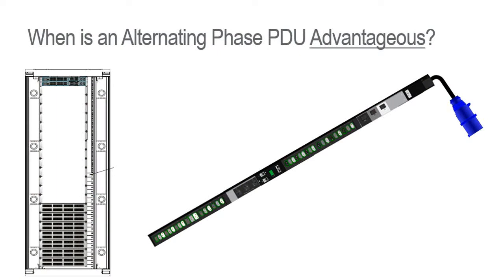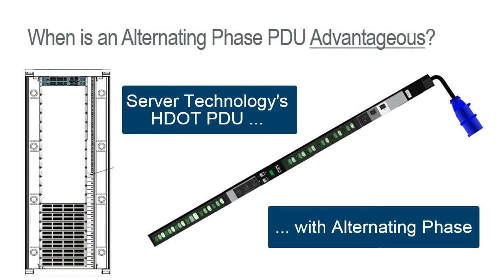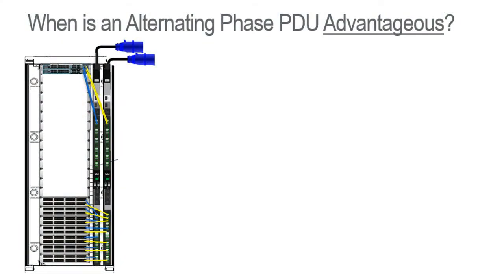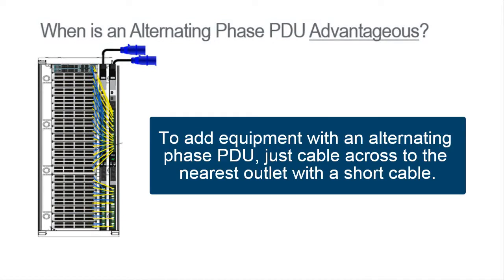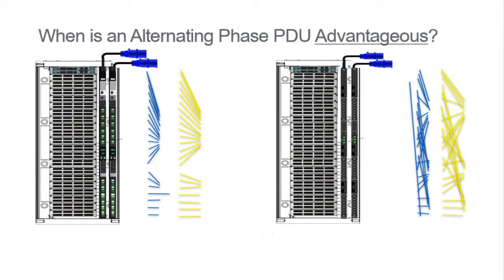Now let's set up the same rack with an alternating-phase PDU, like Server Technology's popular High Density Outlet Technology, or HDOT, and watch what happens with this type of PDU. Remember in our example there was initial deployment of only a third of the rack at the bottom? With the alternating-phase PDU shown here, the rack can achieve balanced loads with shorter cables. As equipment is added, you just need to cable across to the nearest outlet on the PDU with a short cable. Load balancing occurs almost automatically.